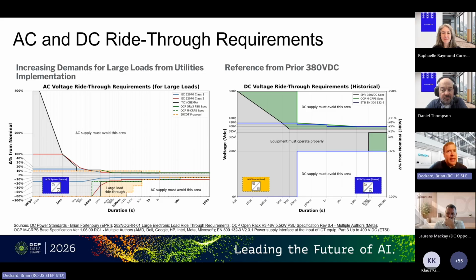Data centers typically have the ability to switch over to backup power to ensure their compute can continue to perform needed functions without interruption. However, this switchover, if not coordinated properly, can result in the potential for grid stability events, as we saw relatively recently in the Northeast. So there's been a high focus on what can be done to ensure better coordination between the loads and the grid.